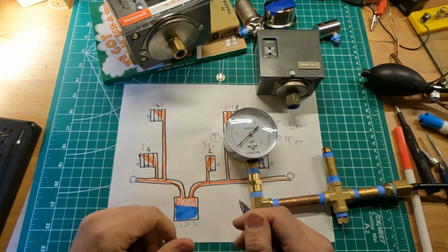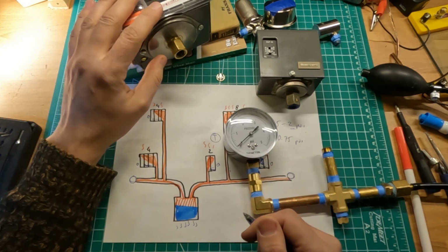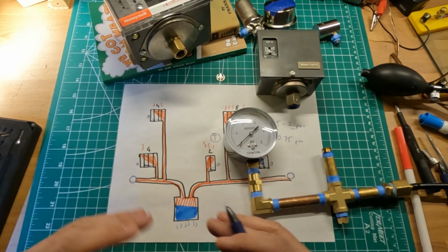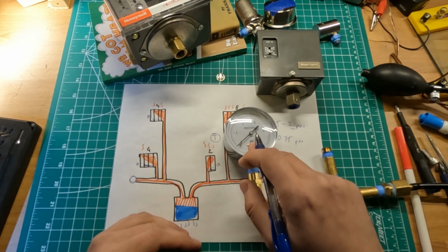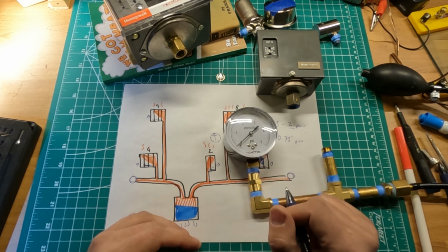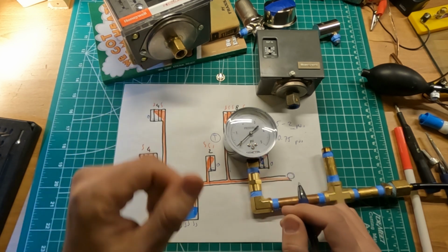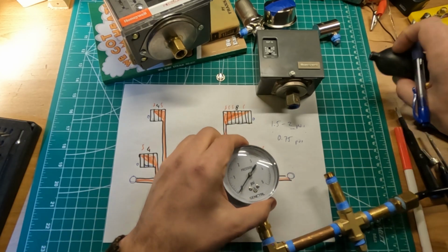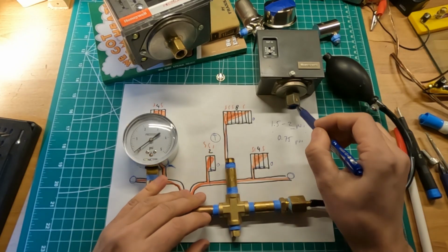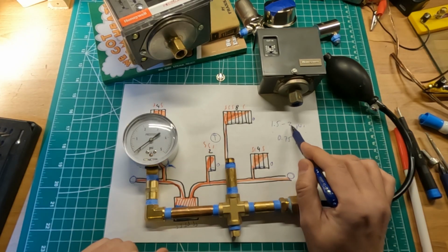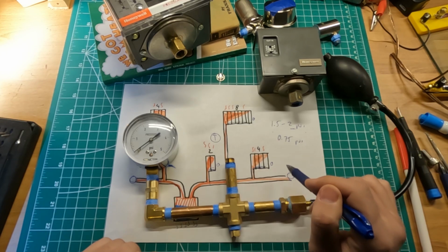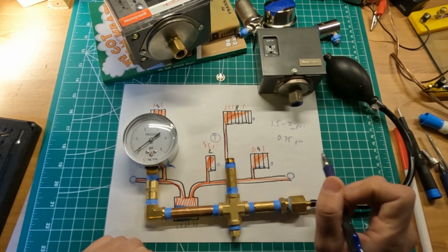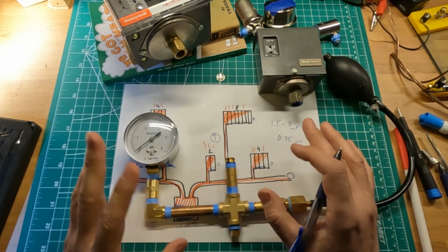Again, it's up to you. Do you want the extra expense of spending $400 for the Vaporstat to make your system work slightly better? Maybe not. It really depends. Definitely get a low pressure gauge and attach it somewhere near your Pressuretrol, so you know what's happening within your system. Anyway, if you only have a Pressuretrol, set your Pressuretrol to shut down the boiler at around 1.5 psi maximum. And if you have a Vaporstat, set your Vaporstat to 0.75 psi maximum. That's that. Hopefully that was helpful for somebody.